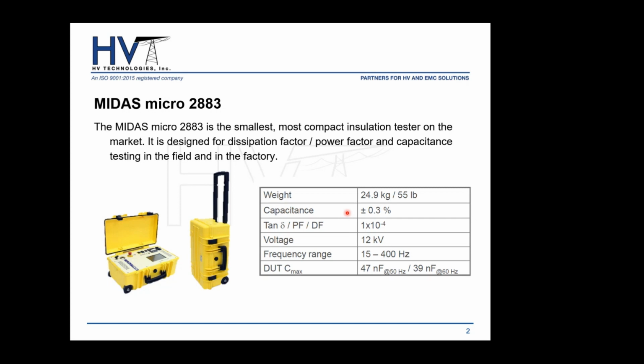Like I mentioned, up to 12 kV output with a frequency of 15 to 400 hertz. So this unit will be able to manage testing any device up to 39 nanofarads at 60 hertz or 47 nanofarads at 50 hertz.